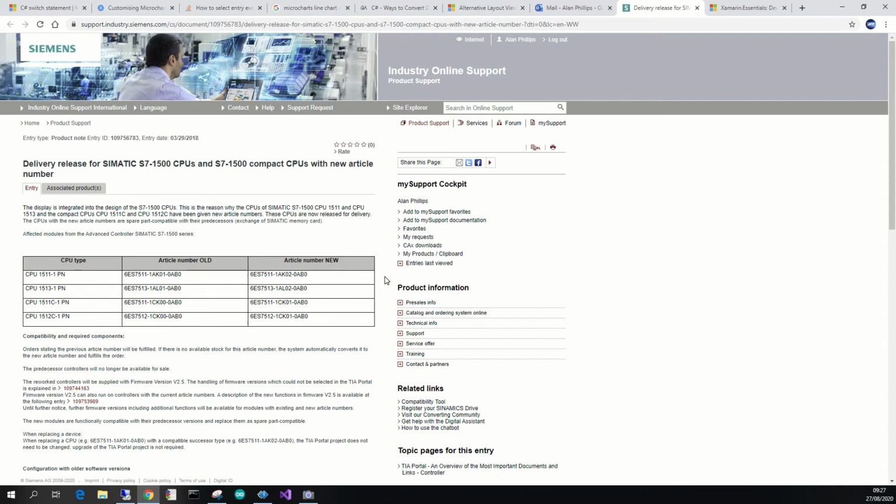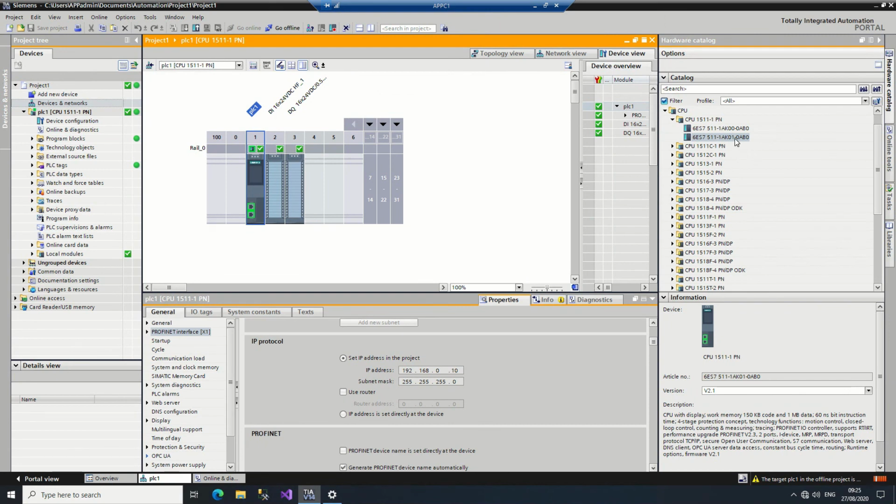Basically, for anyone who comes across this confusion, if maintenance or the project haven't accommodated for spares, it's going to be very confusing when you're writing down that this is actually what's been installed in a CPU swap, in case it ever goes down, and that it won't have any impact. So it's one of those things where it's very unusual. It doesn't feel comfortable doing it off the bat, but this is what Siemens are telling you. So again, you have this CPU, it'll say version 2.5 on it. But when you're actually in the project software, you just select the AK01 at version 2.1.